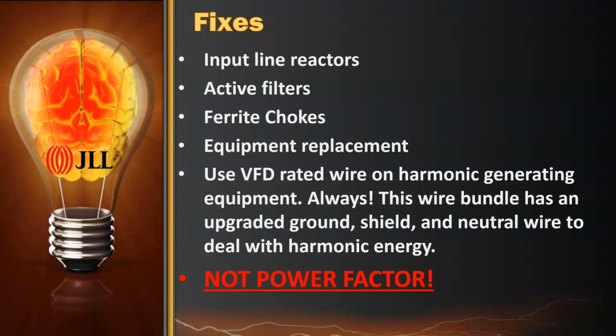Okay. So energy calcs for equipment replacement, like let's put in a new chiller, let's put in new package units, whatever. Do they typically account for reductions in harmonics? Or do you think there should be specific harmonic studies done to calculate the additional energy saving by replacing it? They typically don't, those calculations typically are not done. As a rule, JLL is very recently saying to anybody who is putting anything with a VFD in it in any of our buildings, better have a harmonic filter and prove it. So we are forcing the issue because we see the result of that.